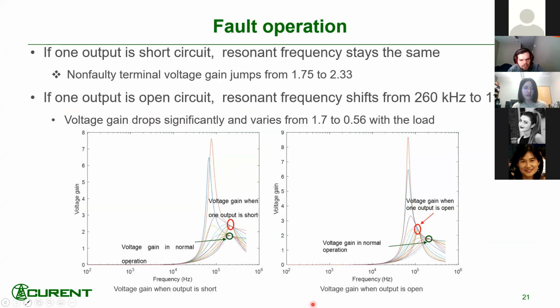And for fault operation, because I have 4 terminals, it's kind of challenging to determine, if one output is short circuit, the impact on the other outputs. So the non-faulty terminal voltage gain would ramp up. And if there is an open circuit, the resonant frequency shifts away and the voltage gain drops.